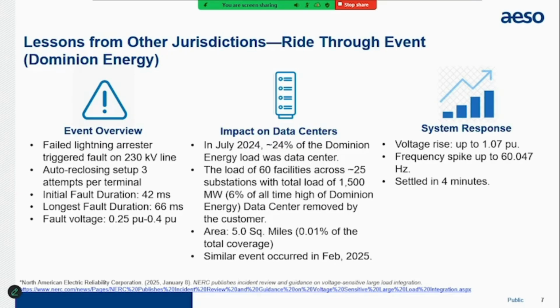After investigation, they noticed that the data centers had transferred their load to backup generation. As a result of this sudden loss of load, there was a voltage rise in the local area where the data centers were located, and a frequency spike in the bulk power system, which eventually settled within 4 minutes. But now imagine this Dominion Energy event, located in Virginia.